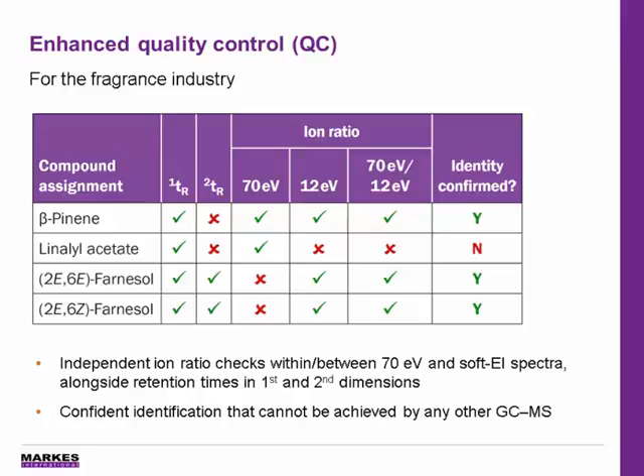This allows additional qualifier checks to be used — for example, ion ratios within and between the 70 eV and soft EI spectra, as well as the retention times in two dimensions. This is extremely valuable for fragrance and aroma applications, where matrix interferences have been known to cause retention indices to fail.